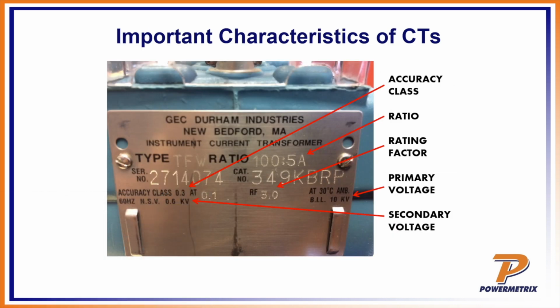And all this stuff is on the nameplate for the CTs. You can see where it shows the accuracy class down there. It says 0.3% accurate, right? And we're going to talk about it in a second, but it says it's 0.3% accurate at 0.1, and we'll talk about that in a minute. We got the ratio, which we talk about a lot. So the ratio for this CT is 100-to-5, okay? So it's 20-to-1. What it's saying is if I see 100 amps primary run through there, I'm going to see 5 amps on my secondary terminals, okay?